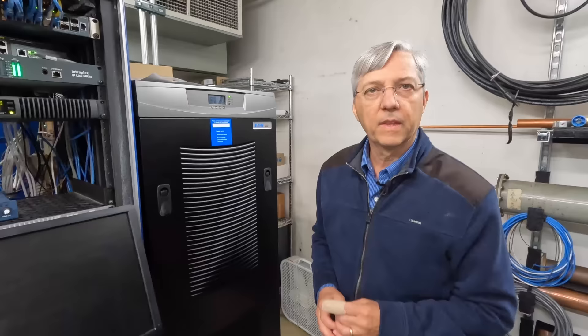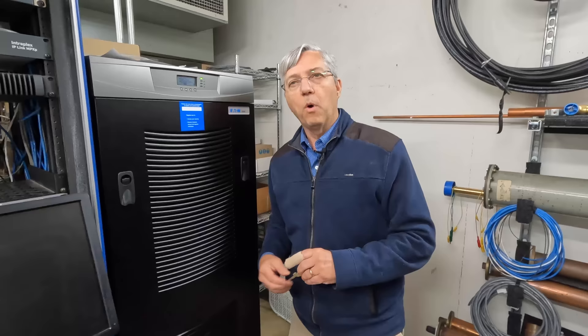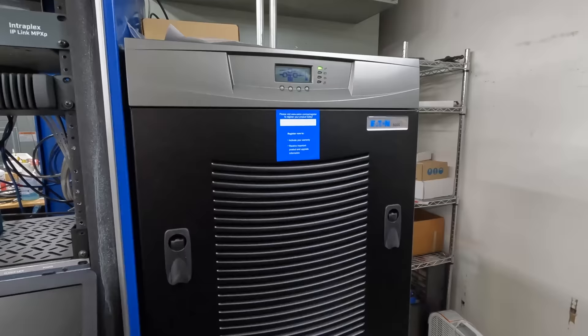So let's say the power to the building is cut. This UPS will kick in right away, but it won't run the analog transmitter — that alone would be too much, and this service covers three rooms. The UPS keeps all the computerized and audio gear running. The transmitter will be up when the generator kicks on about 10 seconds later and everything will be back to normal. The audio and remote control gear — all IP-based — stays running throughout.